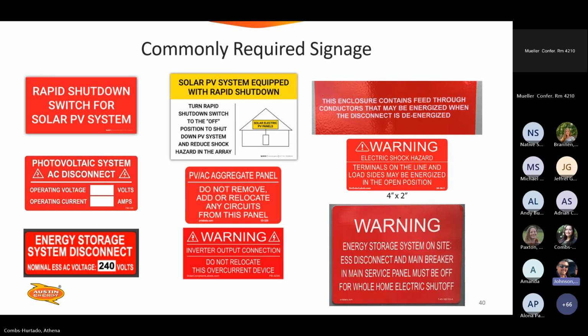Aggregate panel. Do not remove, add, or relocate circuits from this panel. The aggregate panel is not a bonus sub-panel for the house for the extra circuits to be added to. It means what it means. Everything is designed to only withstand what we're doing with it on the solar and the ESS. No additional loads need to be added to that. No car chargers, no landscape lighting, no extras. Inverter output connection. Do not relocate this overcurrent device. If it is for the backfeed breaker at the bottom of the panel, it needs to stay per NEC code at the bottom of the panel as far from the main as possible.